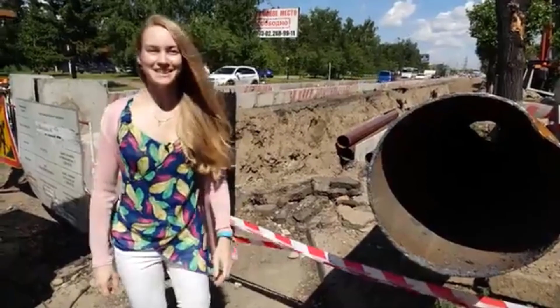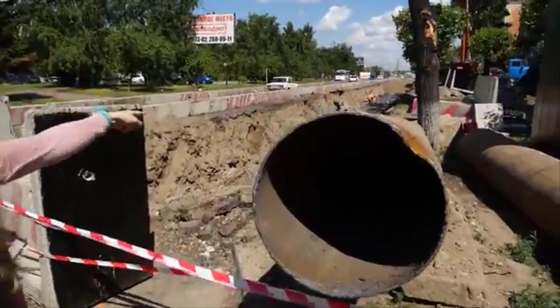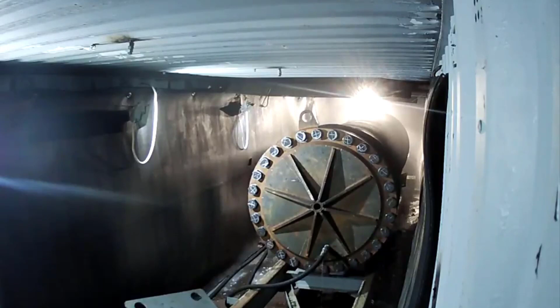Imagine you need to check a heat network with a diameter of 500 mm and a length of 5 km for weak points along the length of the pipeline. What do weak points mean? It is necessary to find those places where in the winter there will most likely be leaks in the pipeline. How to do it? Apply method 16, excessive action. Supply water to the pipeline under pressure 25% higher than the average level, and perform an inspection for leaks. Leak spots are marked and then repaired as planned. There are no leaks during the next winter as usual after such actions.